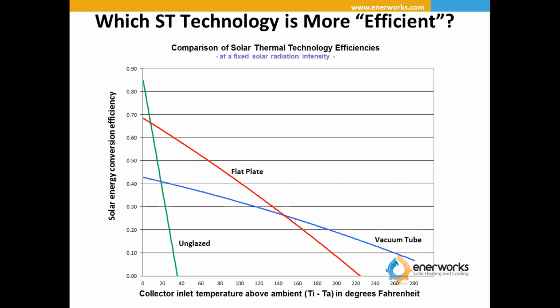And then the last one is vacuum tubes. And keep in mind, these are representations only. There's more and less efficient in each category. Vacuum tubes tend to start out a bit lower, but have a relatively flat efficiency curve. So they're ideal for collecting temperatures as high as 180, 190 degrees because they don't lose as much energy as other products.